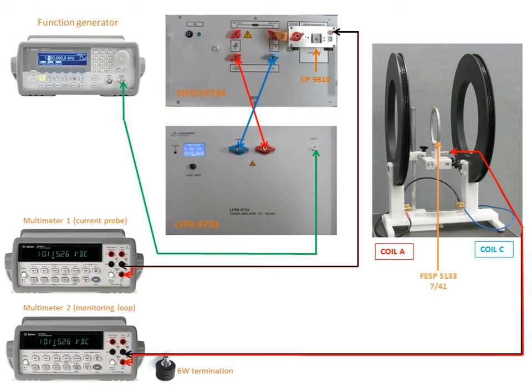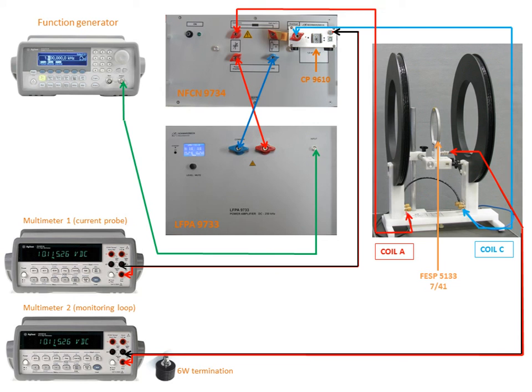The power amplifier is then connected using the provided cables to the compensation network and finally the Helmholtz coil is connected to the compensation network using the MagTest cables.